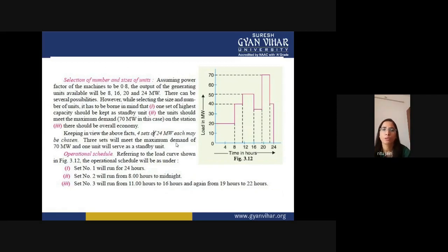So we have to consider that the base load must be continuous, and the number of units which is suitable for base load must be operated, and the units must also meet the maximum demand, which is your 70 megawatt, on the station. So there should be overall economy when you are selecting the units for generation. So we are taking 4 sets of 24 megawatt each may be chosen. So 3 sets will meet the maximum demand.